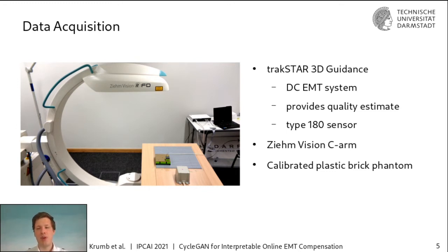We placed this tracker in the vicinity of a Ziehm Vision RFD C-arm, which has a steel enclosure that generates magnetic distortion. For the actual data acquisition, we use a calibrated plastic brick phantom that is placed close to the C-arm at different positions, collecting data in 3 different positional degrees of freedom.